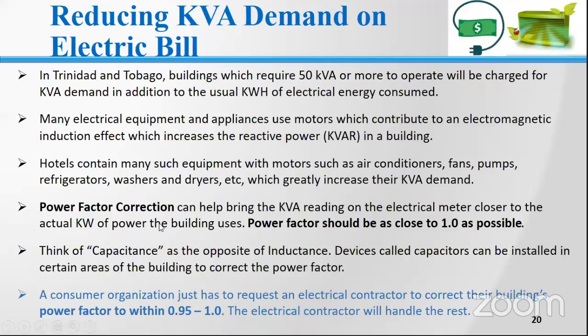What you need is something called capacitance, which you can think of as the opposite of inductance. Devices called capacitors can be installed in your building to correct the power factor. I understand this could be technical and difficult for some people, so I've highlighted this in blue, this is all you really need to know. As a consumer organization, just make a request to any electrical contractor and tell them you want to correct your building's power factor to within 0.95 to 1. The electrical contractor will handle the rest, they'll know exactly what you want, and that's all you really need to know.